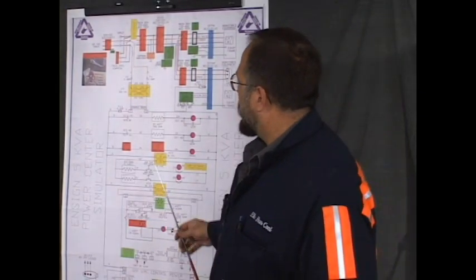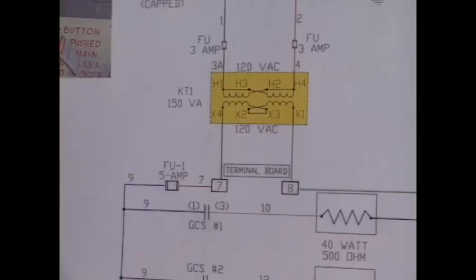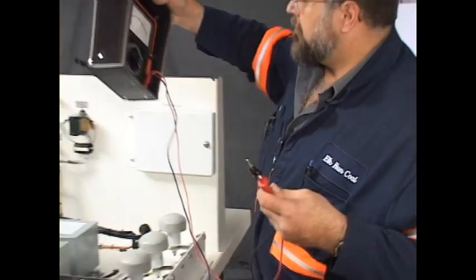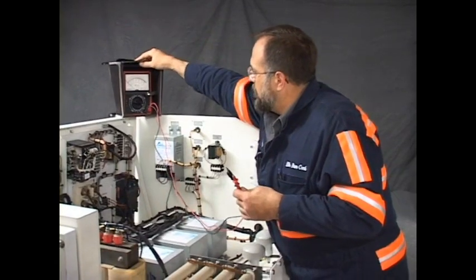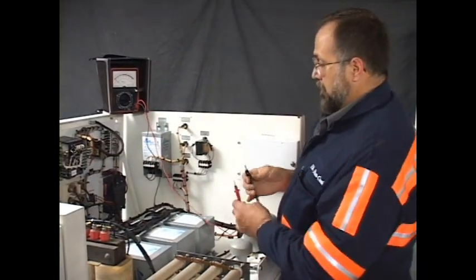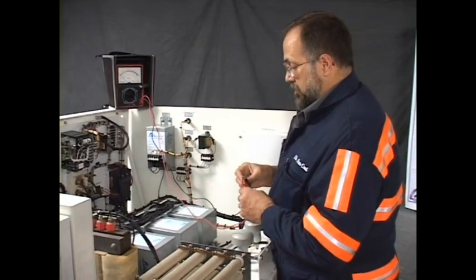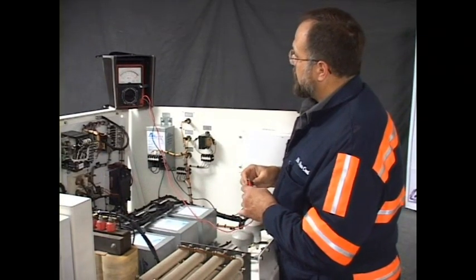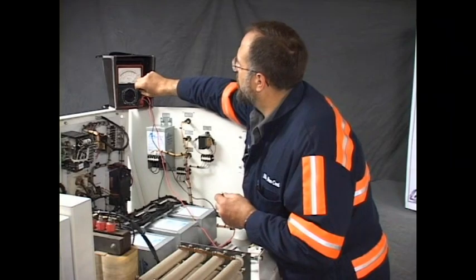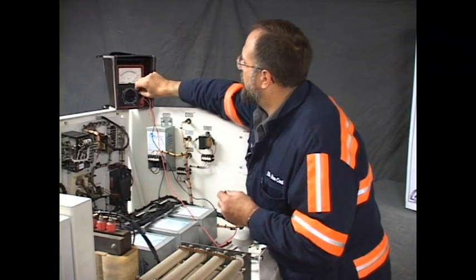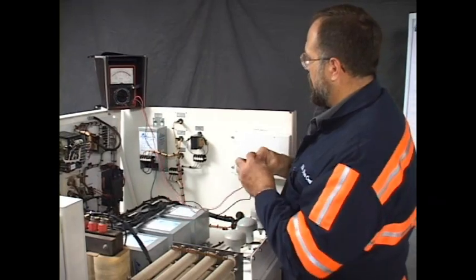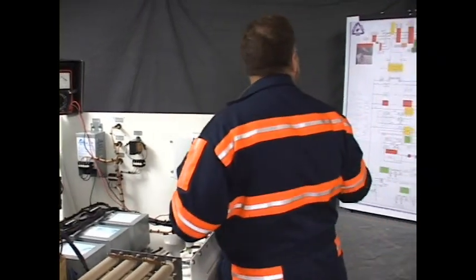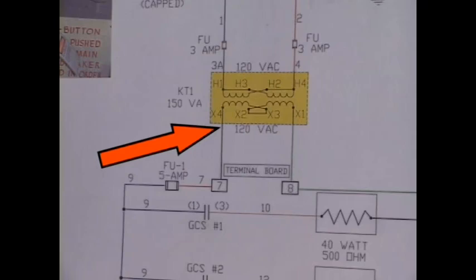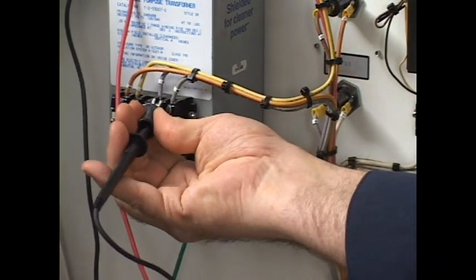So we're going to begin our troubleshooting at the secondary of KT1, terminal X4, the first point that we can access. I'm going to place my instrument up on top here where everyone can see it. Make sure it's stable. Always, before you begin any test, you check your instrument. Zero adjustment. And the secondary of the transformer begins with terminal X4, wire 7. And that can be found right here.